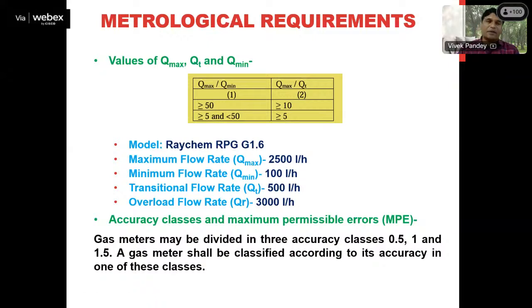Now in the metrological requirement, the next parameter is this. You can see a table is specified, and I just spoke about the 3 flow rates: maximum flow rate, minimum flow rate, and transitional flow rate. Here I have taken a particular example of a gas meter where the maximum, minimum, transitional, and overload flow rates are specified. So how will you check whether the flow rates specified by the manufacturer are correctly given? A manufacturer cannot give just any value for the maximum, minimum, and transitional flow rates, because I told you that between minimum and maximum flow rate, the transitional flow rate is the point where the accuracy changes. Whether that particular point is correctly selected or not is already specified in our rule.